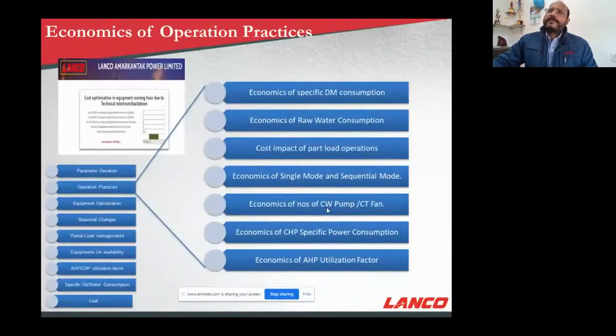Secondly, there are certain operation practices, like economics of specific DM water consumption and economics of raw water, because these are more of monitoring, measurement and control kind of actions, where we see how efficiently the operations are working. Raw water consumption and wastage are reduced. Then the cost impact of part load operation, single mode and sequential mode operation of the turbine. Then the economics of the number of CW pumps and CT fans we are operating. So what were the best achieved earlier has been put into the model. Similarly, specific power consumption of CHP and economics of ash handling plant utilization.